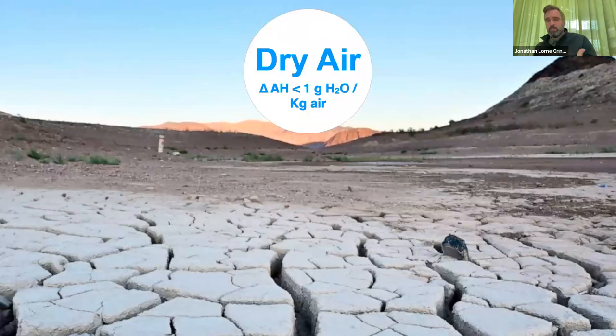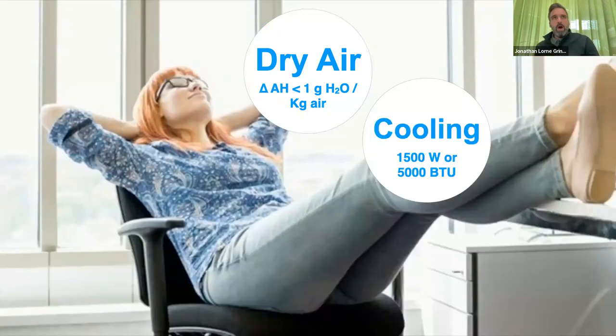We show that we bring in dry air. So the actual absolute humidity of the air coming in does not increase more than a gram. So this is actually saying that fundamentally the system works. We're not inducing more clammy, moist air coming into the building using indirect evaporative cooling. We do a great job of cooling. We get about 1500 watts or about 5000 BTUs. This would be the equivalent of sticking a standard AC unit in the window. But in this case, we're not using vapor compression. We're just using the evaporation of water.